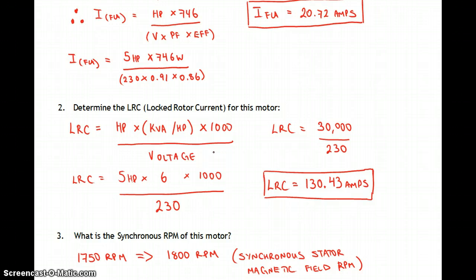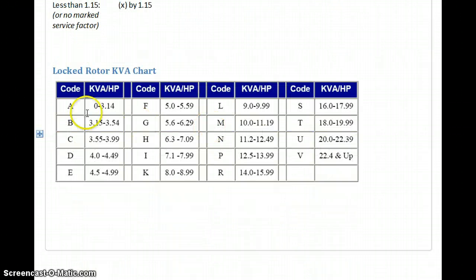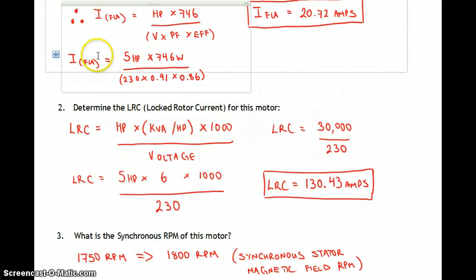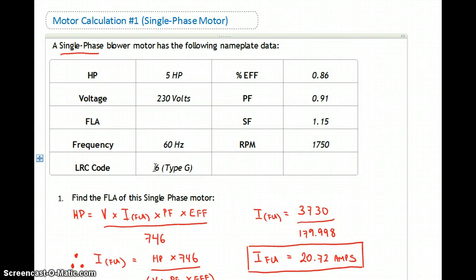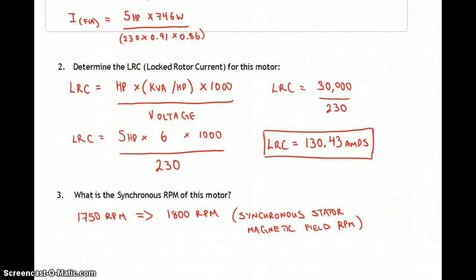Lock rotor current is the starting current, or when too much load stalls the motor — essentially the same condition as startup. Lock rotor current equals horsepower times kVA per horsepower times 1,000 over the voltage. The kVA per horsepower comes from the lock rotor kVA chart. For type G, that range is 5.6 to 6.29. If a specific value is given, use it — here it's 6. So: 5 horsepower times 6 times 1,000 over 230 gives a lock rotor current of 130.43 amps.